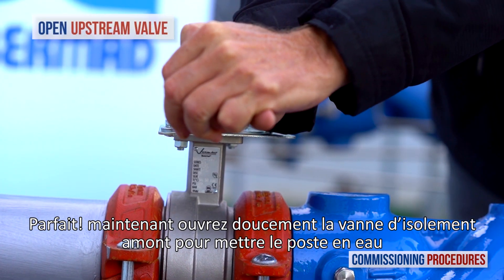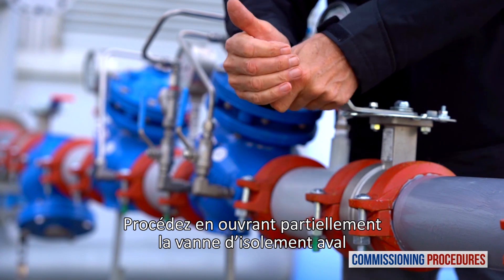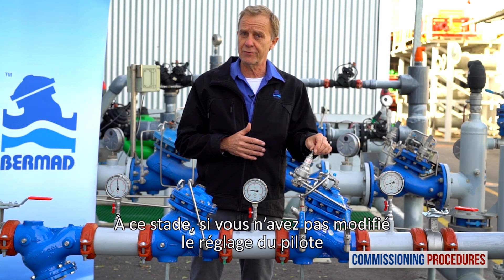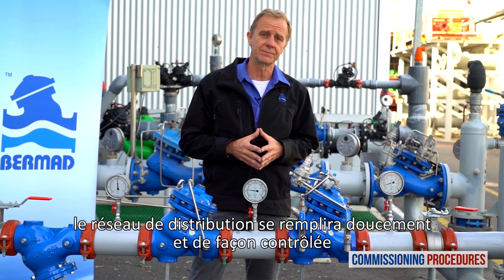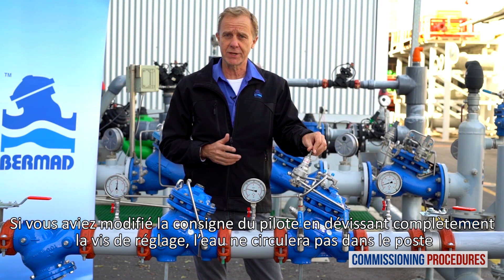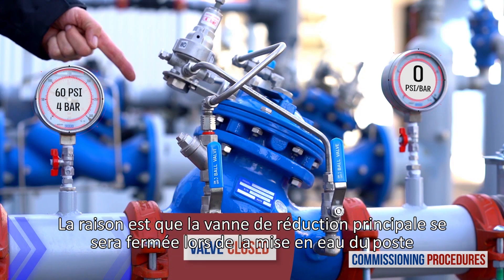Now slowly fully open the upstream isolating valve to fill the station with water. Proceed by partially opening the downstream isolating valve. At this stage, if you haven't released the pilot adjustment screw for recalibration, the consumer's line connected to the station will fill in a slow and controlled manner. All you need to do now is to check that the downstream pressure is compatible with your requirements. On the other hand, if you did release the pilot adjustment screw to calibrate the pressure, water won't flow through the station. The reason is that the main pressure reducing valve will have closed shortly after introducing water to the station.